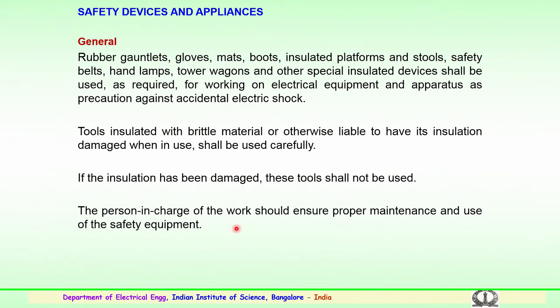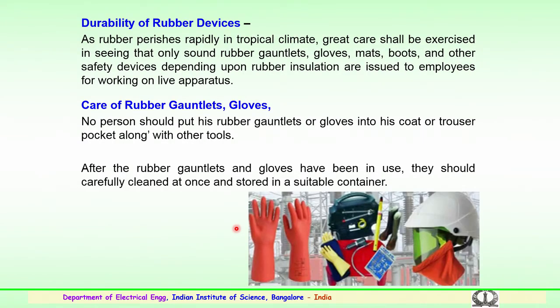Apart from that, several tools which are insulated with brittle material or are otherwise liable to have their insulation damaged when in use shall also be used very carefully. In case the insulation of the tools being used has been damaged, these tools should not be used. So, the person or the engineer in charge of the work should ensure proper maintenance and use of the safety equipment in the substation or in the utility, particularly when attending electrical maintenance works.